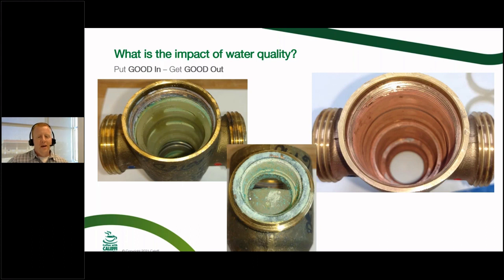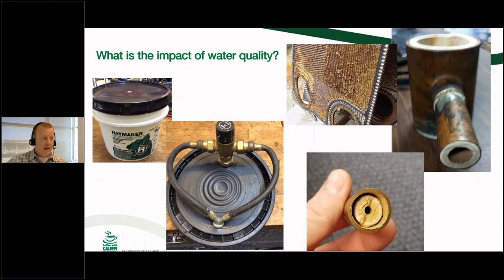Okay, so with that in mind, again, if you've got your potentials for issues with your domestic hot water, it's something that you're going to probably know about already. So definitely keep it in mind when it comes to your mixing valve. Now that could mean that you are cleaning the mixing valves, like our mixing valves, for example, we don't do replacement cartridges. We have replacement bodies available with them. But maybe say you've got this mission critical application that they call up every 6 months or every year or whatever, and oh my gosh, the hot water is not working, you need to get here right away, and it's always my pants are on fire and we need this done right now.